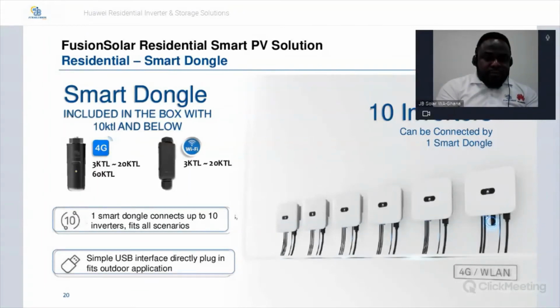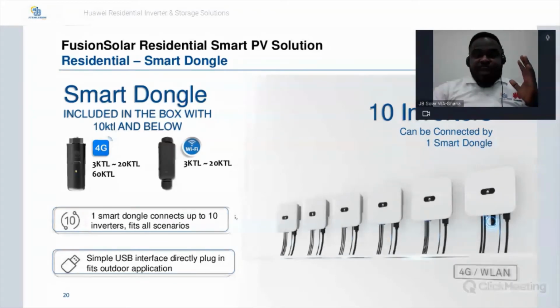Moving forward, another piece of information: if you are using the smart dongle, it can connect up to a maximum of 10 inverters. Remember I mentioned you can cascade a maximum of 10 inverters in one synchro unit. So if you're cascading these 10 inverters, a single smart dongle will work for your system. In the event that you need to connect more than 10 inverters for any Huawei system, the smart dongle will become deficient, it can't work.